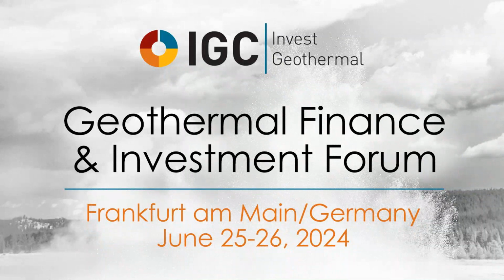Why was the plant in Turkey chosen with one turbine and two cycles instead of two turbines? The main point is that the configuration with two pressure flows going into the same turbine has the advantage of one single turbine machine instead of two, so it has a significant cost reduction and also reduction in the size of the foundations. It is a very compact machine, and it is allowed by the radial outflow configuration. It wouldn't be possible with other kinds of turbines.